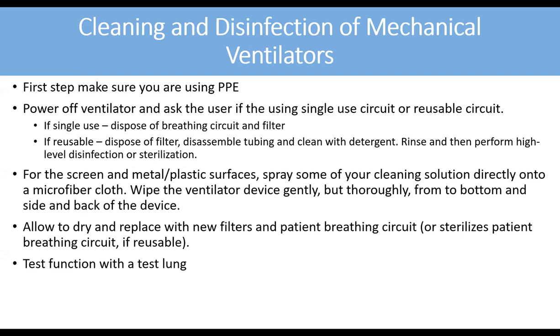For the screen, it's almost the same. For the screen and metal or plastic surfaces, spray some cleaning solution directly onto a microfiber cloth and wipe the ventilator device gently but thoroughly, from bottom to top, side and the back of the device, all that. Allow it to dry, replace with a new filter circuit, sterilize the breathing circuit if reusable, power up the unit, and test function with the test lung.